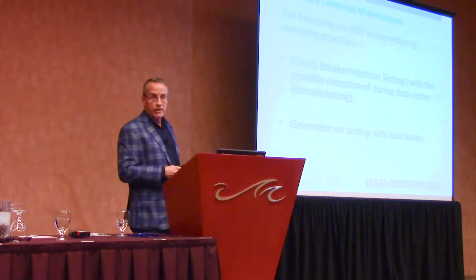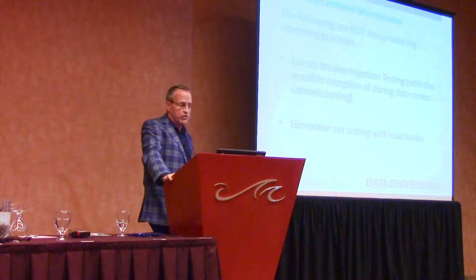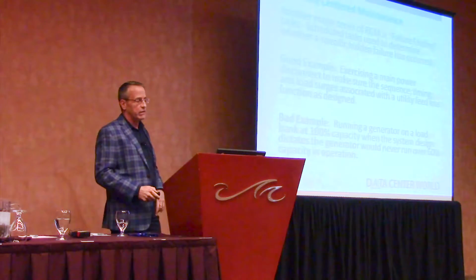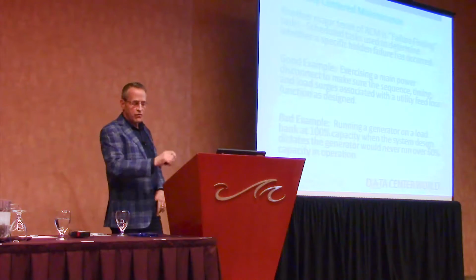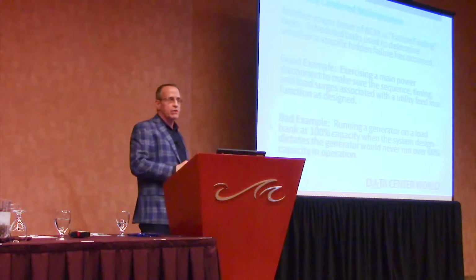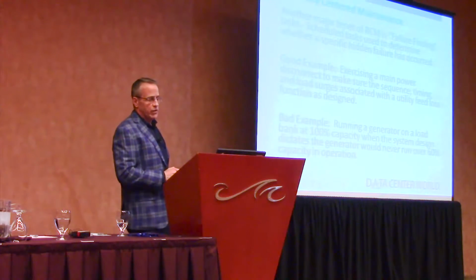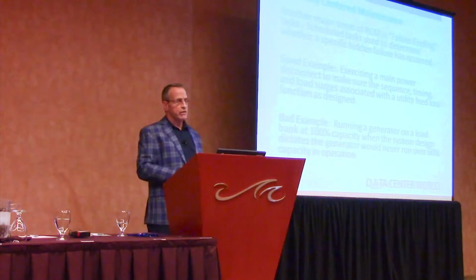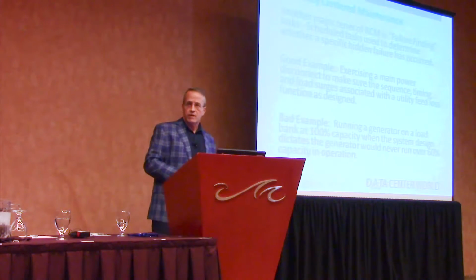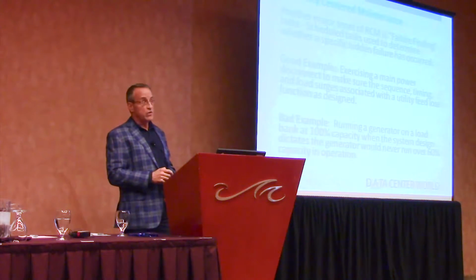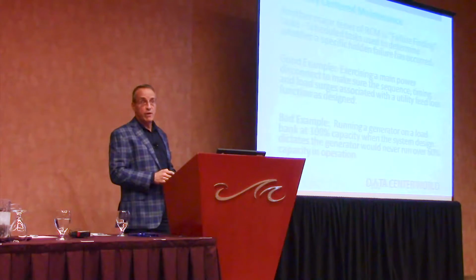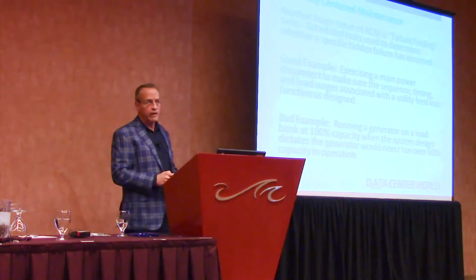One thing that evokes a lot of impassioned discussion is generator set testing with load banks. That's a deliberate, stress-inducing practice, and it goes into failure finding. I jumped to this slide because we talk about generators here more, but a good example of failure finding I already covered: the only way to find out if losing utility power is going to work for you and your systems is you have to do the big nasty. You have to pump up the big breaker, close your eyes, elevate your pucker factor, and go.